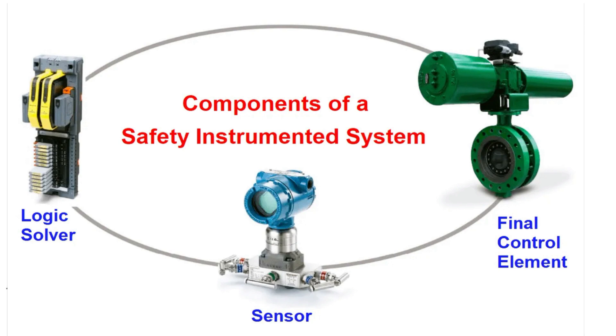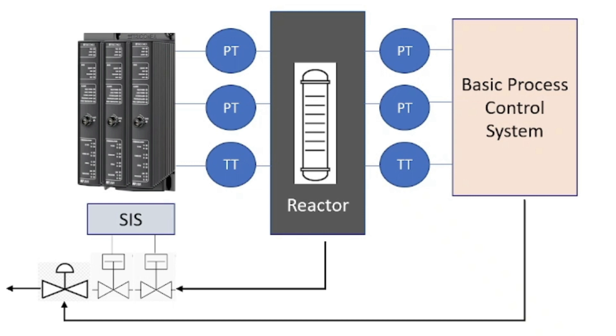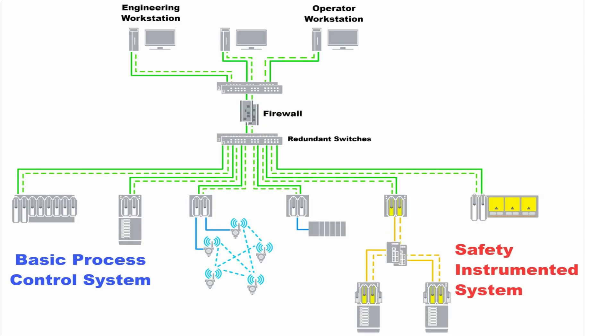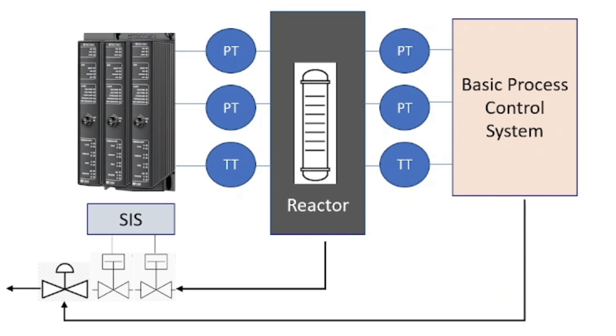A Safety Instrumented Function (SIF) is an engineered system typically comprised of sensors, logic solvers, and final control elements. Its purpose is to bring the system to a safe state when predetermined thresholds are violated. These systems are basically focused on the safe shutdown of the system if some logic is triggered or some threshold is met.